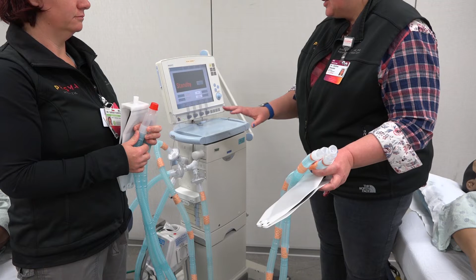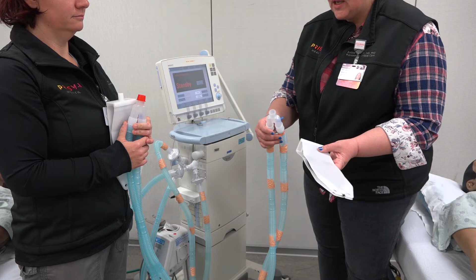So the first thing that you're going to do is make sure you have a cap on one of the patient's circuits, because if you don't have a cap, then you're going to have an open system. So what I would do is place the Y connector onto a test lung for patient A. This is our patient A. And then turn on your ventilator. Give it a second. So we have it set in pressure control mode. Our low minute ventilation alarm is going off because I actually have it set already.